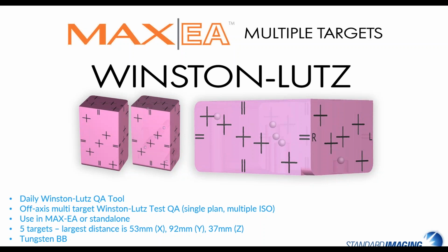And so the targets are spaced apart. You can see here the largest distance is quite far apart, so it creates a robust analysis of your multiple Winston Lutz test. The targets are made out of tungsten BB, so it has high attenuation. It will show up really well in your MV.